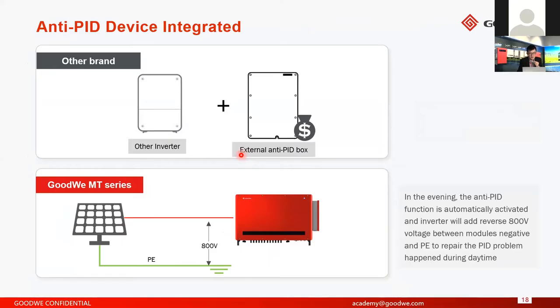Here is about Anti-PID. I think PID is also a serious problem in India, because India, as already mentioned, is very hot and very humid, especially in the summer. So if you don't use bifacial modules, the two-glass modules, just the normal modules, it's very easy to have the PID problem. So if you want to avoid the PID problem, it's better you order an inverter that already integrates the Anti-PID board inside, like GoodWe. We integrate the Anti-PID board inside, so you don't need to buy the external box.